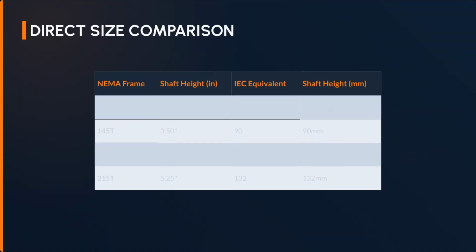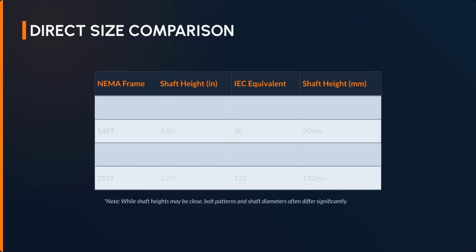When making a direct size comparison, note that while shaft heights may be close between NEMA and IEC equivalents, bolt patterns and shaft diameters often differ significantly.